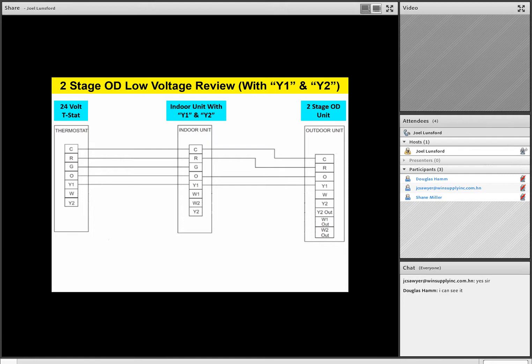Now, because we're looking at a heat pump, we're also going to have an O terminal. That O terminal from the thermostat will go all the way through again, from O on the thermostat to O on the indoor unit to O outside, all the way through, just a straight circuit. Now, if you have a Y1 terminal on the indoor unit, typical wiring is going to be Y1 from the thermostat. This would be your first stage heat pump operation on a two-stage unit. So Y1 from the thermostat to Y1 on the indoor unit to Y1 outside. So all those wires, those are, you might say, hard wires that are going to be wired in, and these are wires that are always going to just go straight through, so to speak.